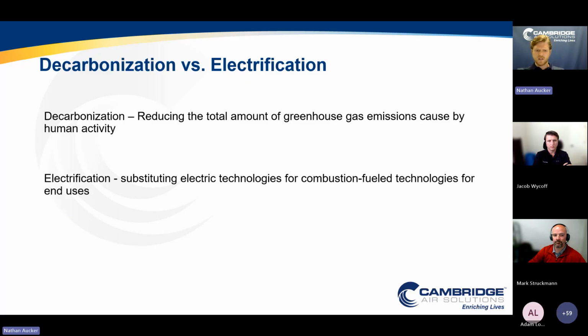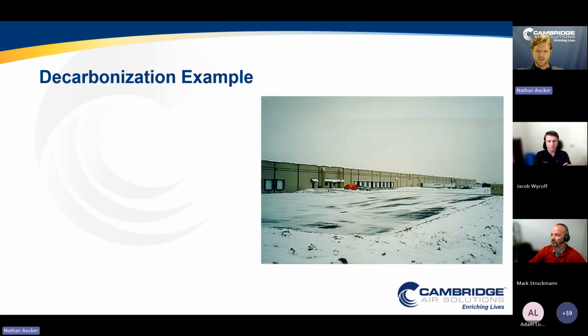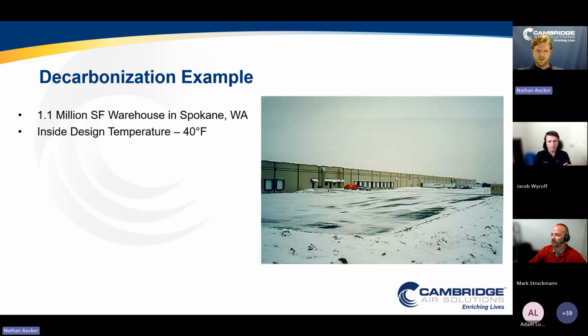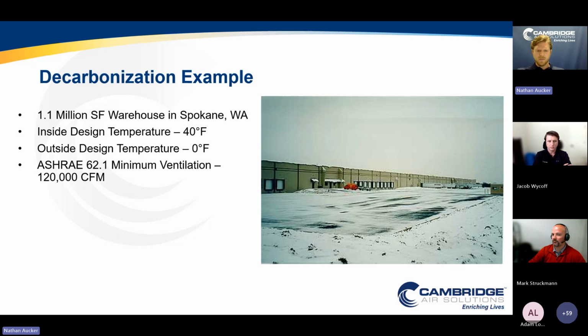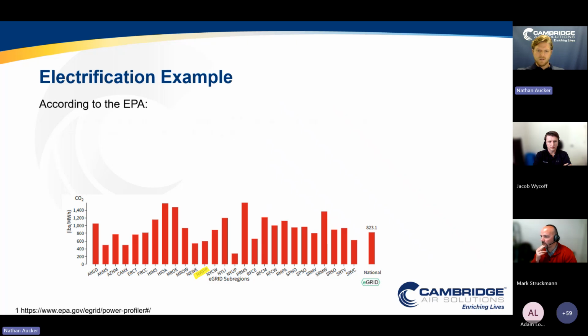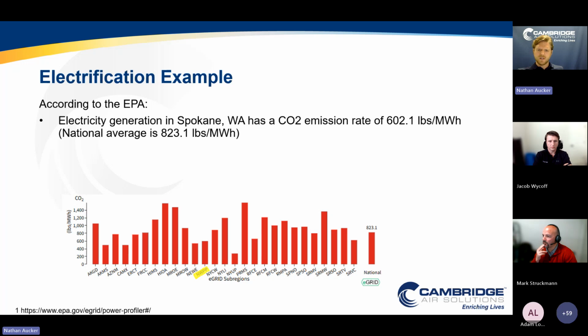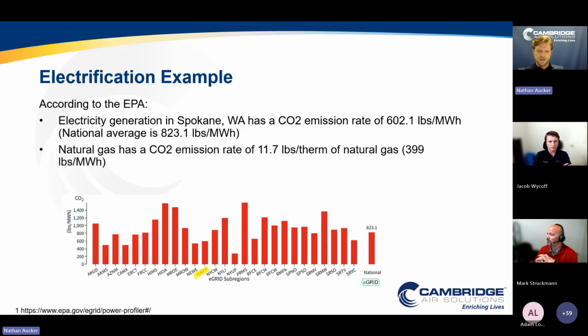Let's look at an example of a warehouse. This is a warehouse in Washington, a 1.1 million square foot warehouse. Within this warehouse, the inside design temperature is 40 and the outside design is 0. There's a minimum ventilation requirement of 120,000 CFM, and the total building heat load in this case would be 3,525 kilowatts. According to the EPA, Washington has a CO2 emission rate of 602.1 pounds per MWh, and a CO2 emission rate for natural gas of 399 pounds per MWh. We'll keep these 602.1 and 399 in mind as we jump to the next example.